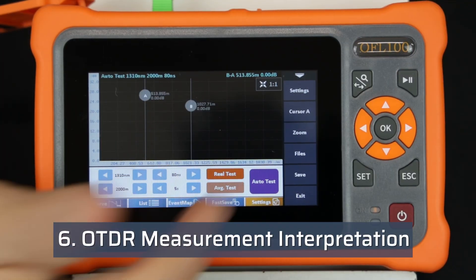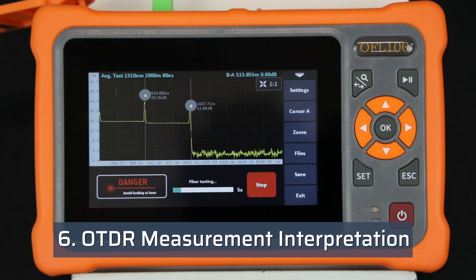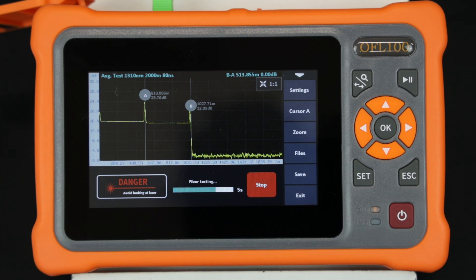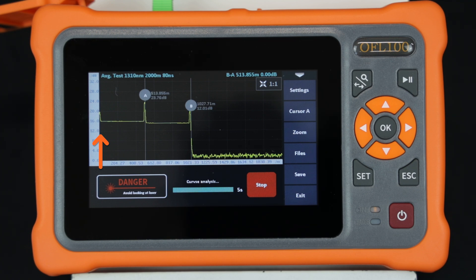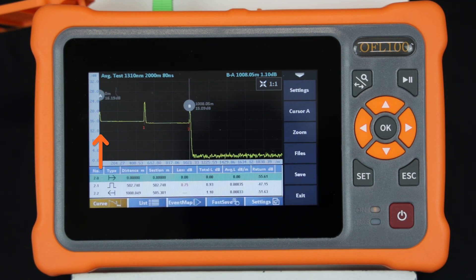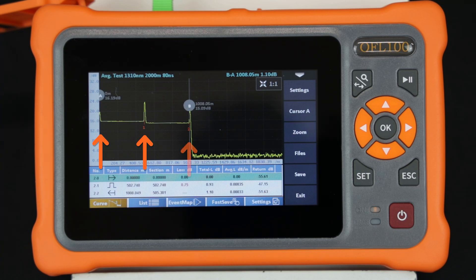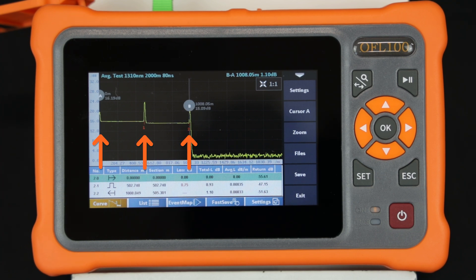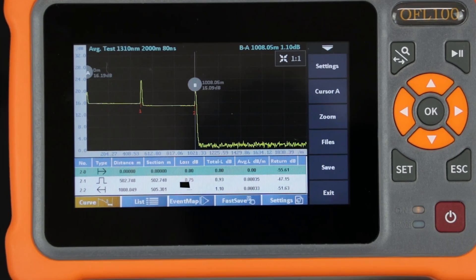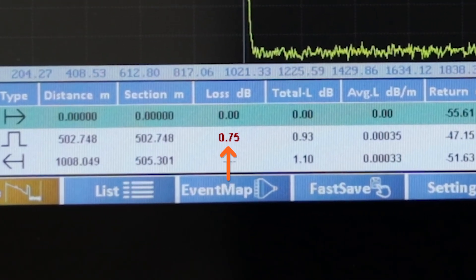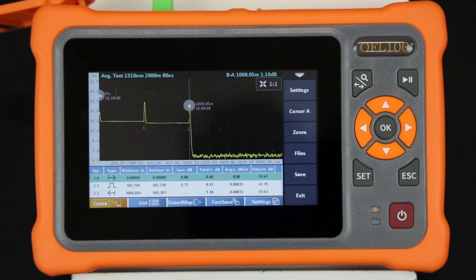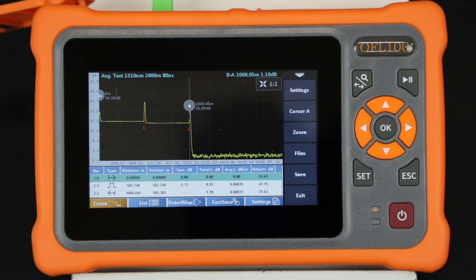Here is a typical OTDR trace using the OFL-100 to measure a 1,000 meter length of fiber with a bad connector at approximately the 500 meter mark. The bulkhead is on the left-hand side and is represented as event 0. The connector that has a high insertion loss is event 1 and at the end of the fiber is event 2. The connector at event 1 is likely contaminated and requires cleaning. The insertion loss is 0.75 dB and is displayed in red as it exceeds the allowable threshold of 0.2 dB. The red indication aids the technician in identifying the fault and that action needs to be taken to resolve the problem.